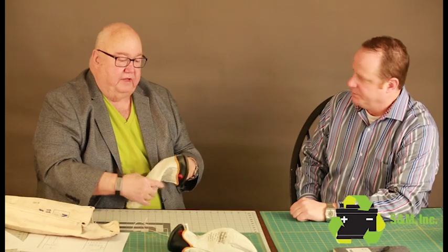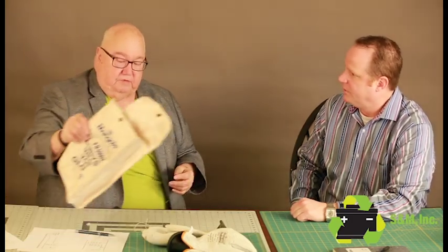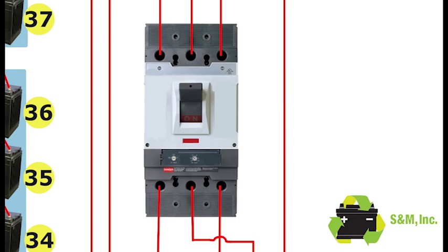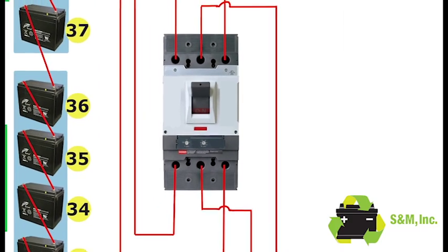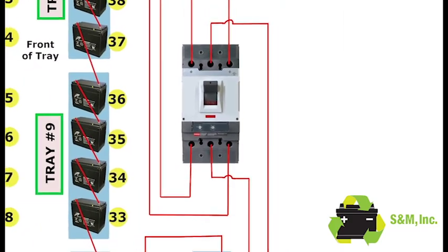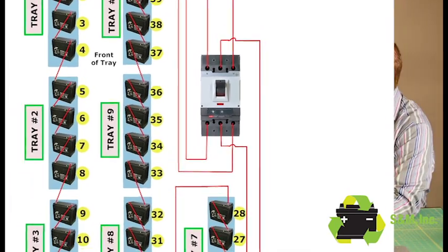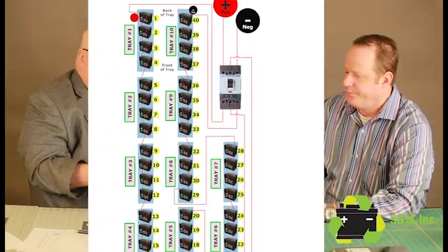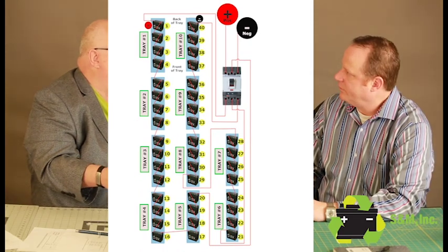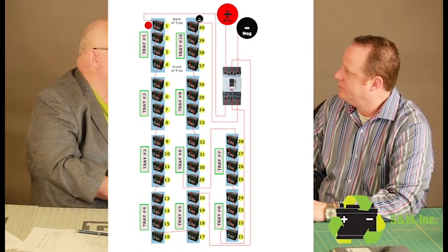For years in the UPS world, they've been taking a 3-pole switch and using the two outer poles as disconnects for the extreme positive and extreme negative ends of the battery string, then using the middle pole to break them into two series strings for maintenance. This will be that concept, just more of it, to break it down into smaller series strings for smaller voltage parts of a string so a technician can work on it. We also found out that a 3-pole switch is cheaper than a 2-pole switch in a lot of cases because they're selling more of them.